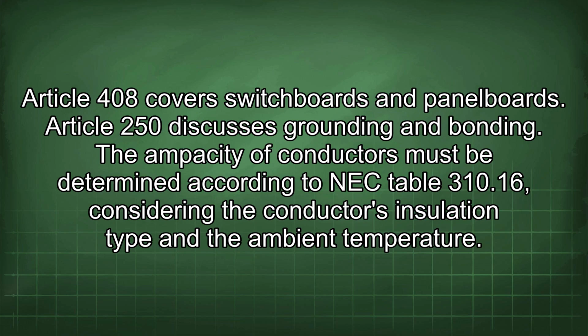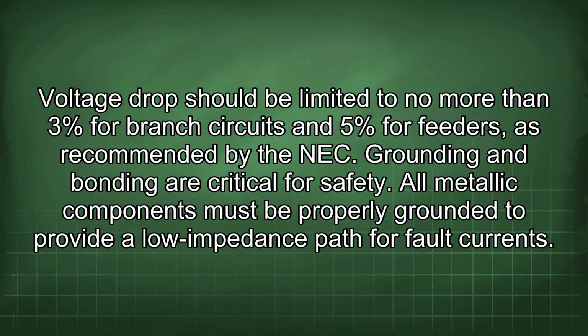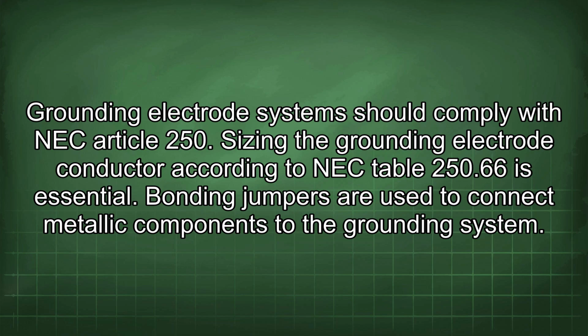The ampacity of conductors must be determined according to NEC Table 310.16, considering the conductor's insulation type and the ambient temperature. Voltage drop should be limited to no more than 3% for branch circuits and 5% for feeders, as recommended by the NEC. Grounding and bonding are critical for safety. All metallic components must be properly grounded to provide a low impedance path for fault current. Grounding electrode systems should comply with NEC Article 250.